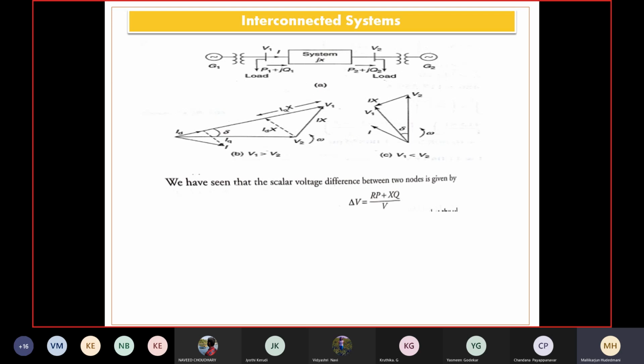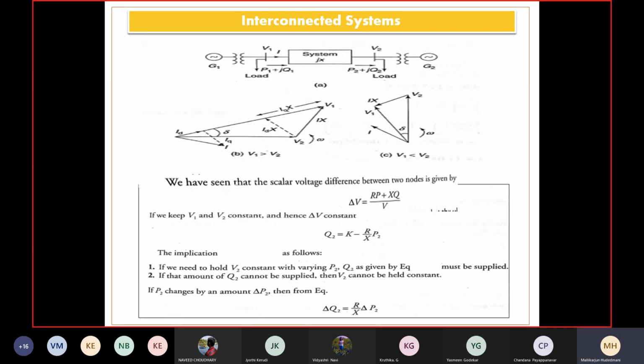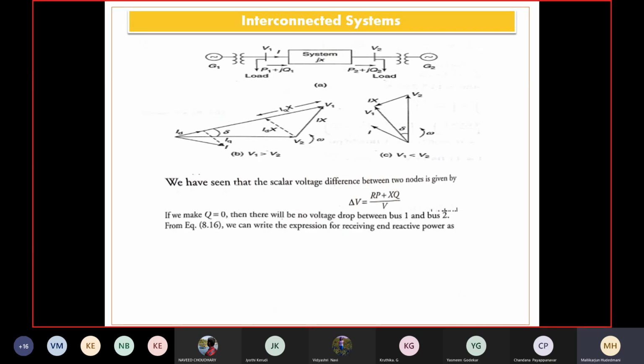The difference in voltage between two nodes is given by delta V equal to (Rp plus Xq) by V, which can be written if you make Q equal to 0. Here, Q equal to 0, reactive power equal to 0, then there will be no voltage drop between bus 1 and 2. It means if we make Q equal to 0, reactive power absorption itself 0, definitely reactive power is the culprit, the cause for change in voltage. If you make it 0, no more drop in voltage between bus 1 and 2.